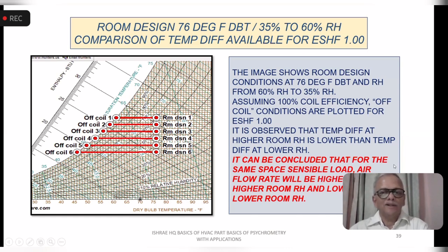So it can be concluded that for the same space sensible load, airflow rate will be higher for the higher room RH, if you want to maintain higher room RH, which is say 60% or 55%. When we say higher, we are always comparing with something which is lower. So if I take the lowest and the highest, you see the kind of delta T available for the two. So practically halfway, which means the air quantity will be practically double if you want to maintain 60% as against 35%. That's the moral of the story.